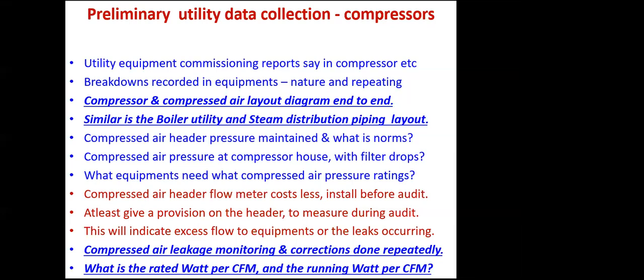So that is why wherever you buy the compressor, you don't buy it for the rated pressure operating. If my operating pressure is 7 bar, you cannot buy the compressor for 7 bar. You have to buy a compressor for 9 to 10 bar only. Then only you operate the compressor derated at 7 bar, or whatever operating pressure is required. The compressed air flow meter is going to cost less. It is around a lakh. Before it was 3 lakhs, 4 lakhs. Now it is costing only a lakh.